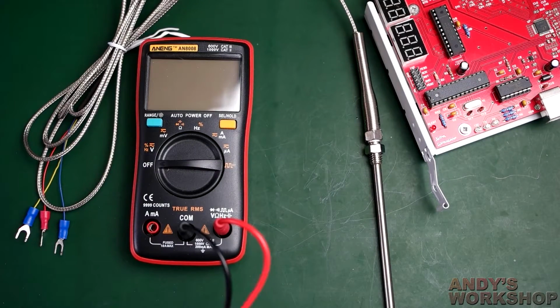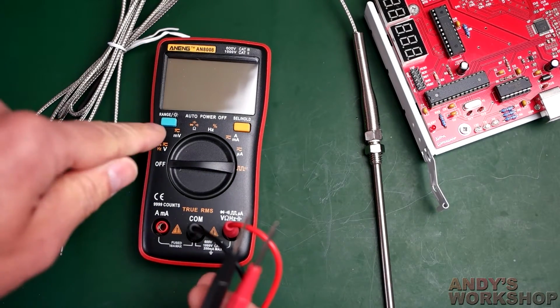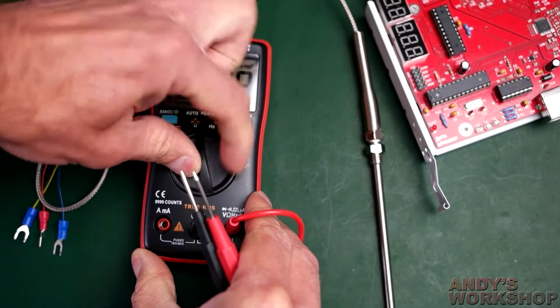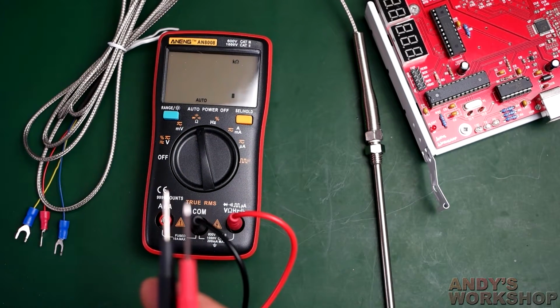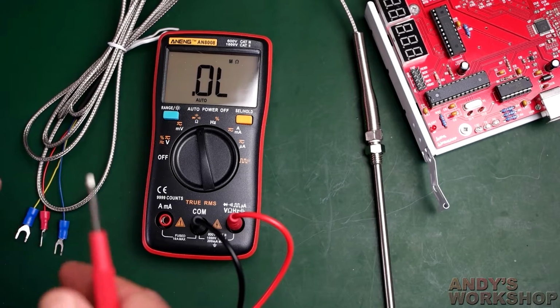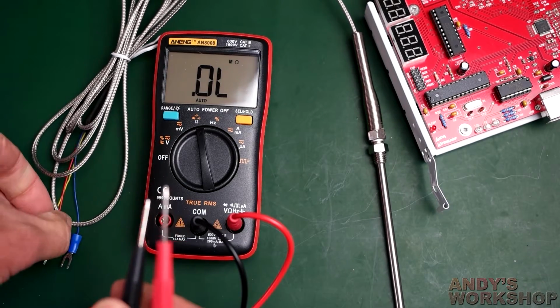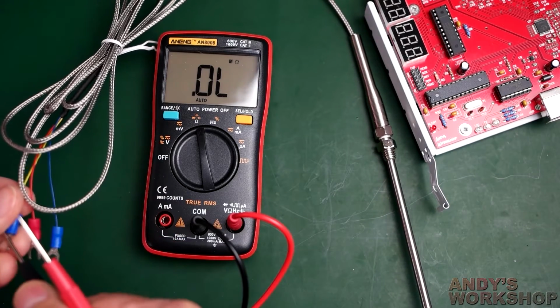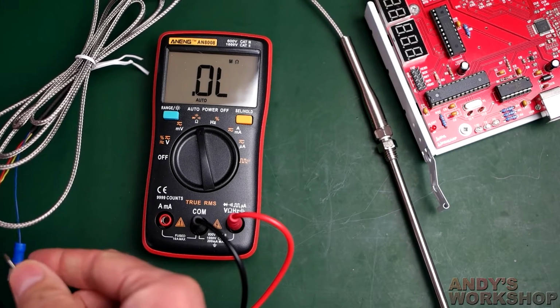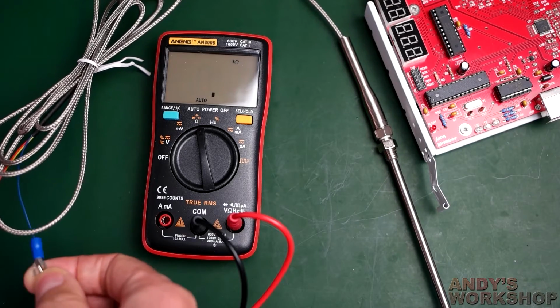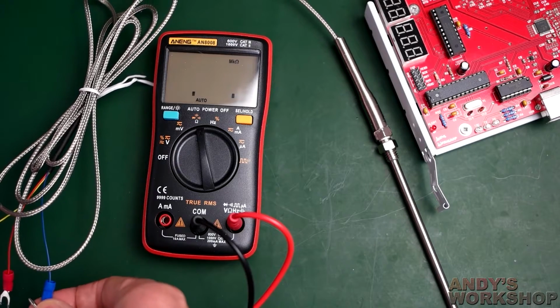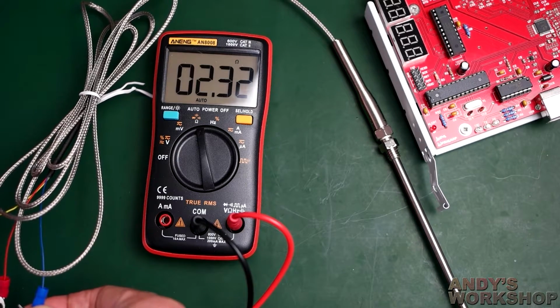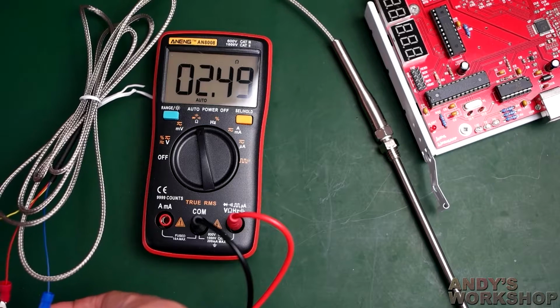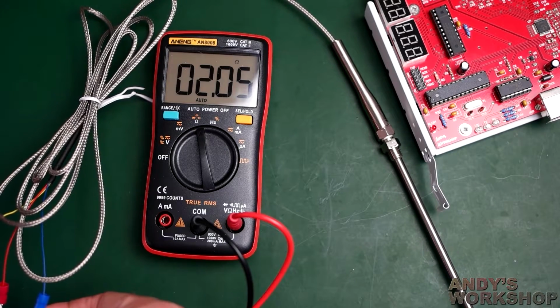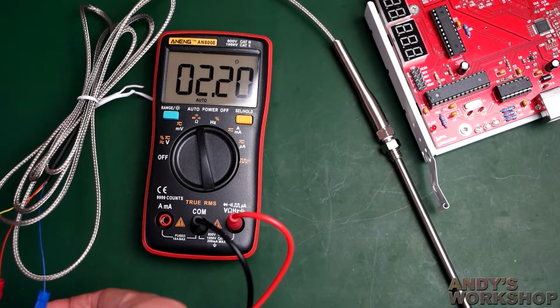Okay, so let's have a look. Cheapo meter time. This is accurate enough. Let's switch it on. Wait for it to do stuff. Right, let's have a look firstly at what the lead resistance is. This will include the resistance of the probe leads and the multimeter leads. Let's see if I can get a good contact here. And it's thinking. We have about, of course, about 2 ohms. Bear that in mind. I can't null out the resistance on this cheapy meter, but it's just 2 ohms, you can remember that.